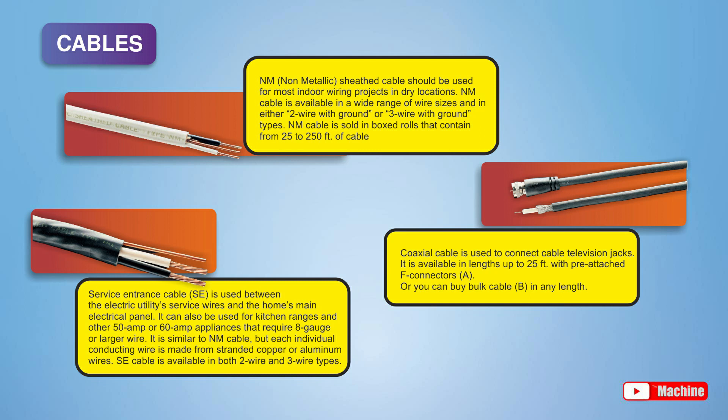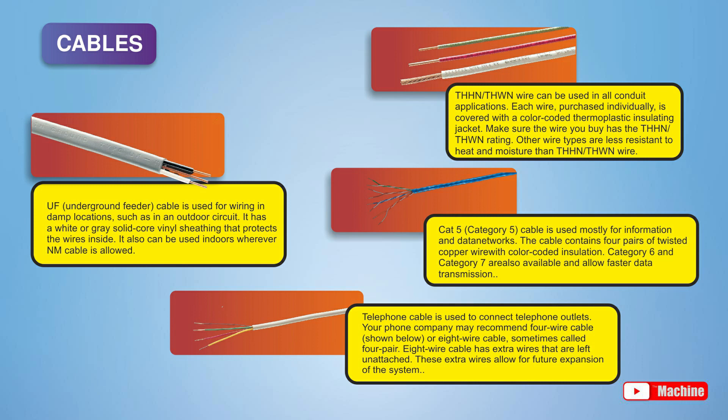Here are some cables usually used at your home. Coaxial cable for television antenna. NM, or non-metallic sheathed, used for most indoor wiring projects in dry locations. Service entrance cable is used between the electric utility's service wires and the home's main electrical panel. THHN or THWN, a thermoplastic high heat resistant nylon coated wire, used in all conduit applications. CAT5, or Category 5 cable, is used mostly for information and data networks. UF cable is used for wiring in damp locations, such as in an outdoor circuit.